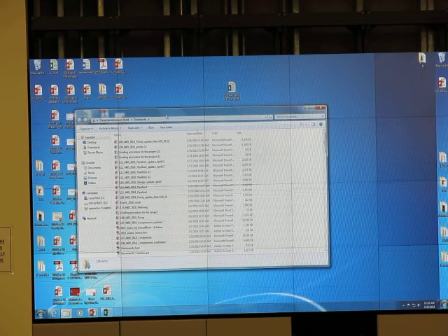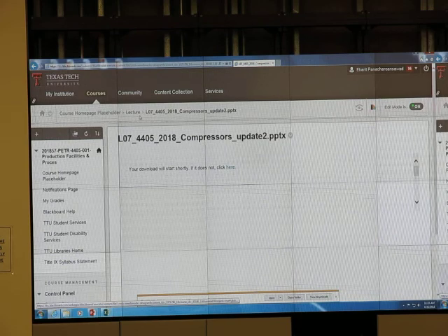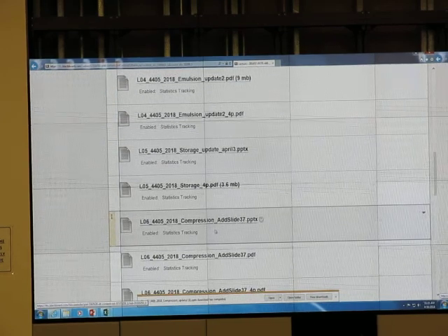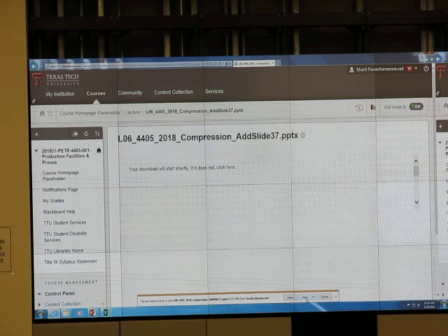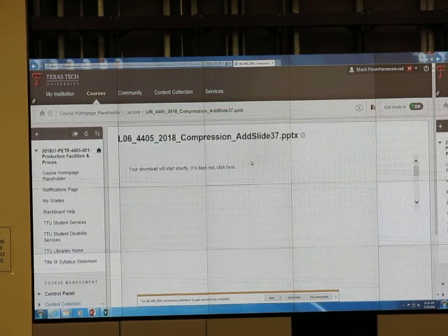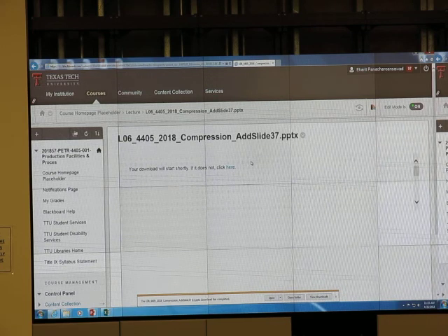Content of the exam, we start from L07. I think it's 07. Compressor or 06? Is it 06? Lesson 06, yes. Okay, there's a mistake in the slide about parallel pumps. If I put two pumps in parallel, we double the flow rate. If we put two centrifugal pumps in series, we double the pressure. Okay?